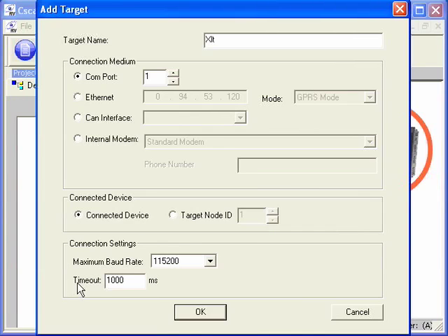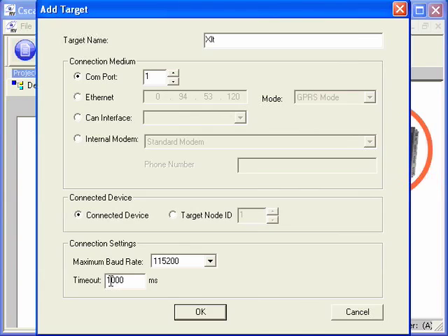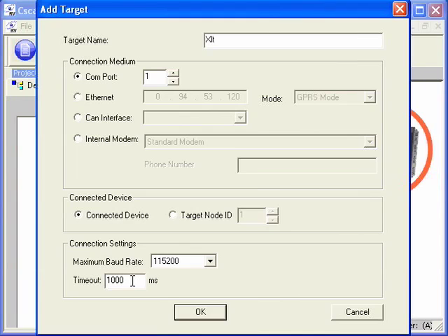The final setting is the connection settings. This allows us to adjust our baud rate and change the timeout. Our one second timeout is fine for our direct connection. If we were using an indirect connection, such as over the Internet or through a cellular modem, we would want to increase this.